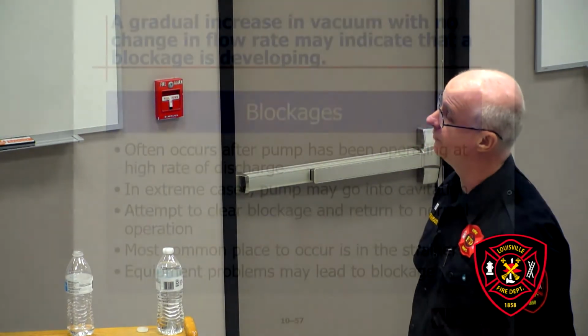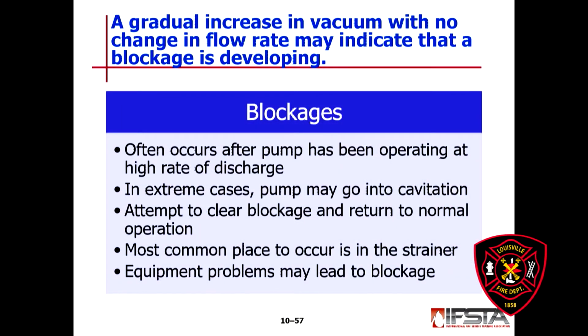If you start to have a gradual increase in the vacuum with no change in flow, you haven't increased your throttle, but you notice the vacuum going up, maybe the engine RPMs start to go up, it may indicate that a blockage is developing. In extreme cases, the pump may go into cavitation.